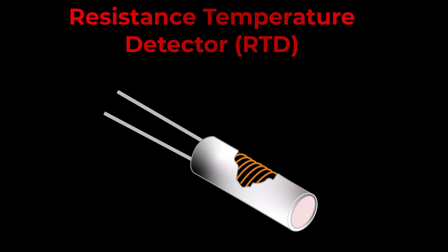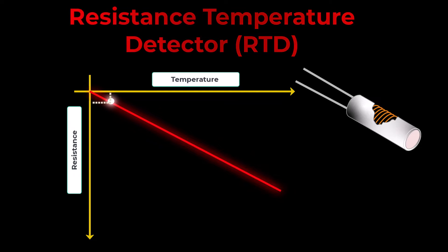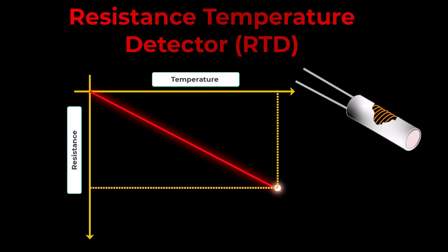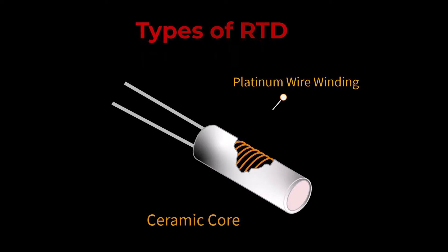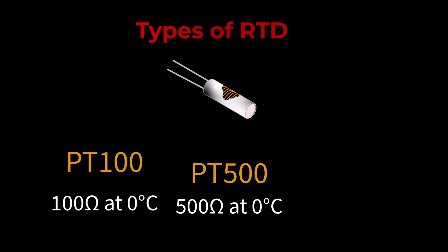RTDs are typically made of pure metals, with platinum being a common choice due to its stable and linear resistance-temperature relationship. As temperature changes, the resistance of the metal changes proportionally. The RTD is connected to a measuring instrument that sends a known electrical current through it. The voltage drop across the RTD is measured, and the resistance-temperature relationship is used to calculate the temperature. Common types include PT100, PT500, and PT1000, denoting different resistance values at zero degrees Celsius.